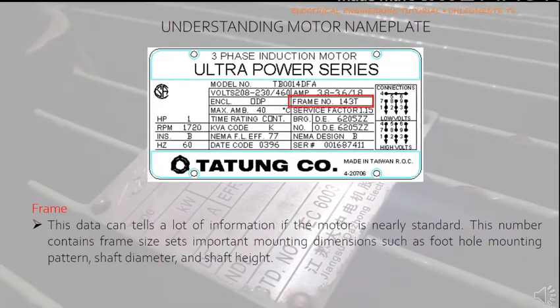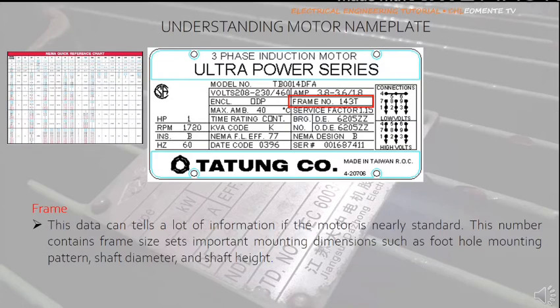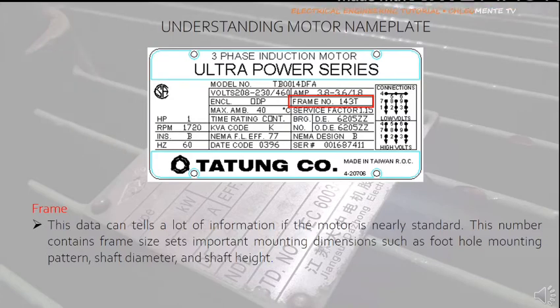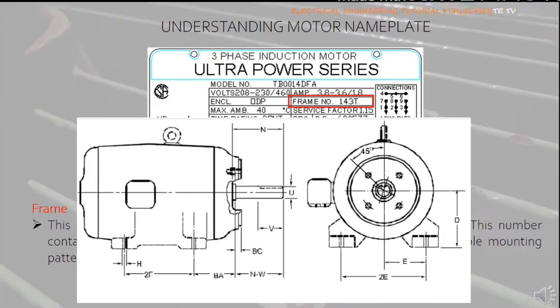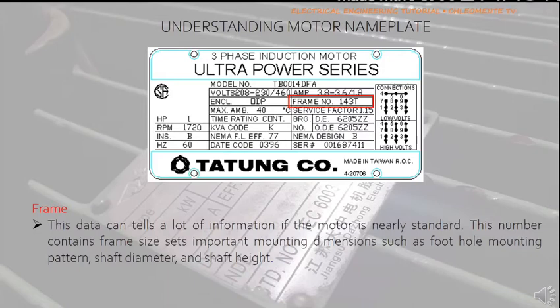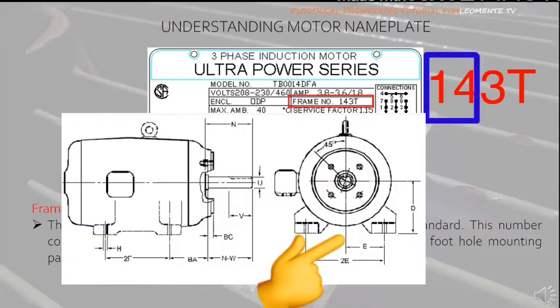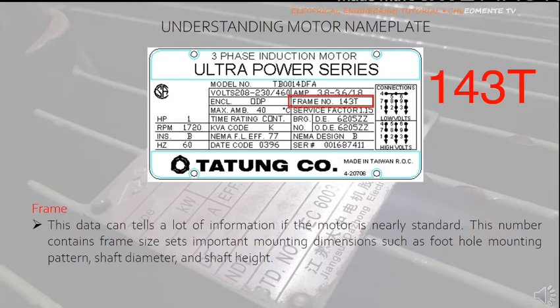Frame: This data tells you a lot of information if the motor is nearly standard. It is given by the NEMA frame designation, which includes frame dimensions such as foot hole mounting pattern, shaft diameter, and shaft height from foot to the center of the motor shaft. In this example, this 1 HP motor has frame number 143T. The first two digits, 14, divided by 4 equals 3.5 inches — the distance from the center of the shaft to the center bottom of the mount. The letter T means the motor is of the 1964 or later T-frame vintage.